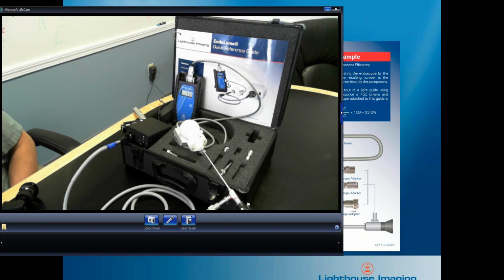43, okay. Yep, 42.5, 43 lumens. It moves around just a little bit, but that's normal. So 43 divided by our earlier output of the cable we measured as 380 lumens. We're getting about 11.3% transmission through the scope.